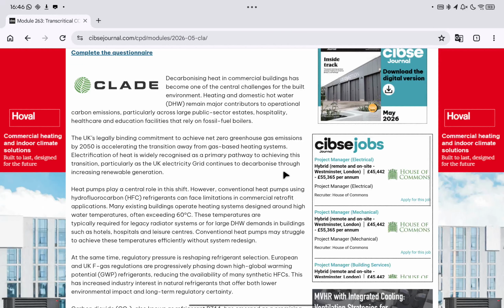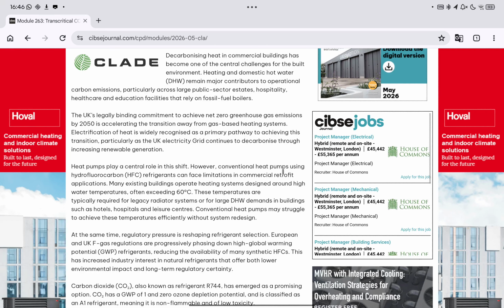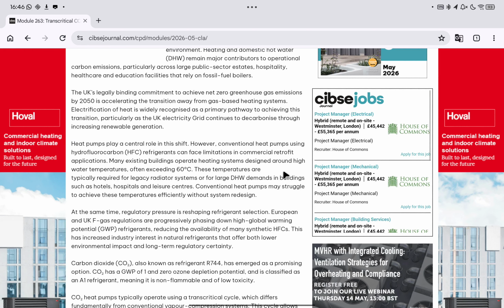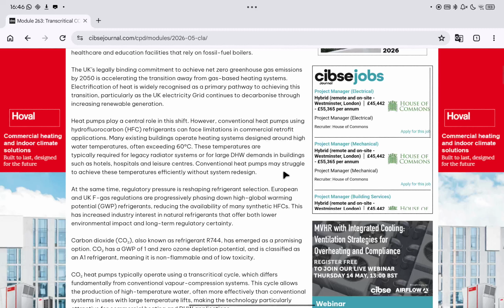Many existing buildings operate heating systems designed around high water temperatures, often exceeding 60 degrees C. These temperatures are typically required for legacy radiator systems or for large domestic hot water demands in buildings such as hotels, hospitals, and leisure centres. Conventional heat pumps may struggle to achieve these temperatures efficiently without system redesign.